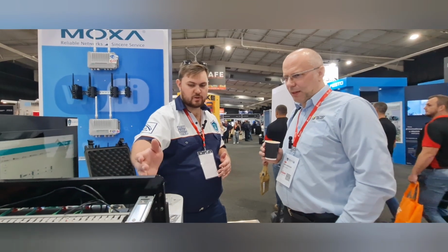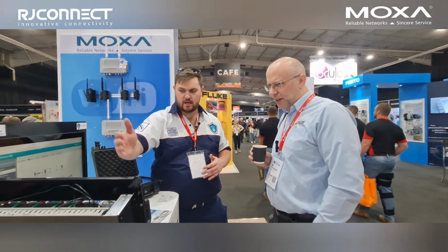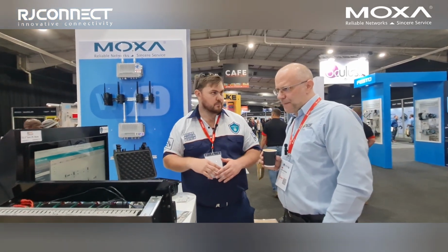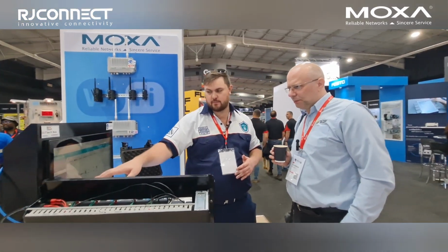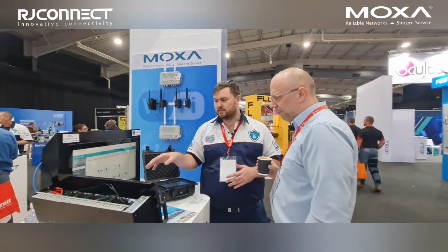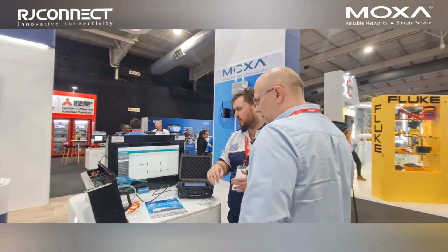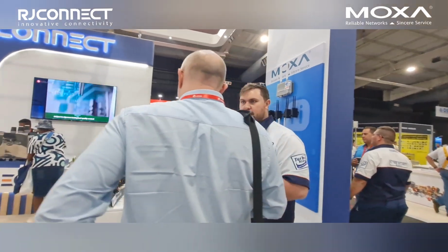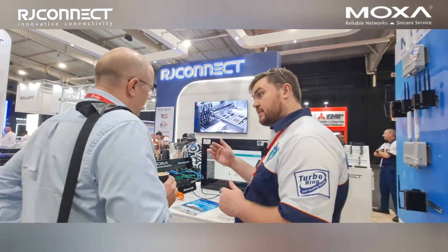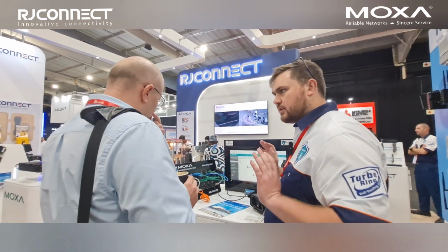To this, you have a couple of access points, a couple of clients, and your standard switches with your fiber. Then what we do is we'll basically set up a redundancy ring. That means that if anything happens, if one of your switches goes down or one of your machines goes down, you'll still have constant communication. It recovers within 2 milliseconds, so if anything happens in that process, you don't miss a message, nothing goes wrong.